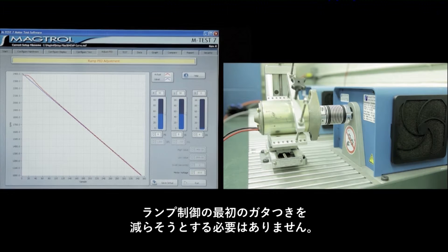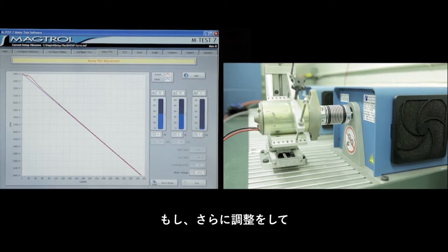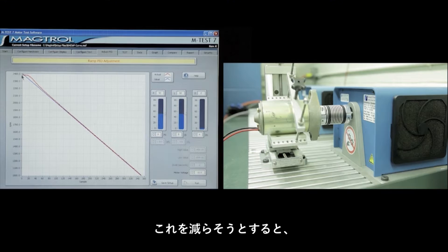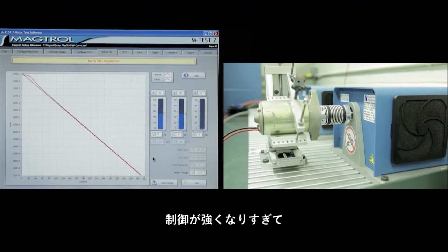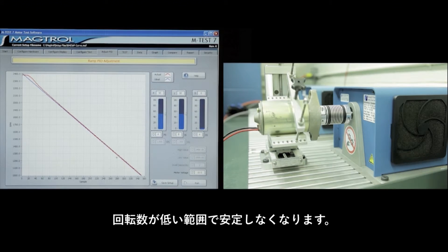It's not necessary to remove this bump at the start of the ramp. In fact, if you continue to make adjustments to remove this, you'll find that you've overcompensated and your system will probably become unstable down at the lower speeds.